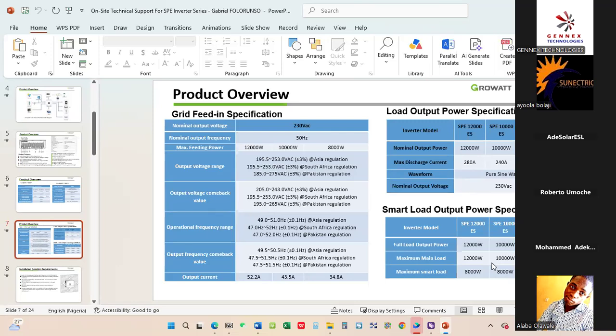Now for the smart load, the good news is that once you hook up all these loads to any of the three family members, they can accommodate a whopping 8,000 watts of smart load. Meaning, let's assume we're working with the 12,000 ES — you can dedicate 8,000 watts as smart load and the remainder for the backup section. But if you're working with the 8,000 model, you can choose to do, say, 4,000 for smart load and 4,000 for backup, depending on what you have at the site or based on the customer's request.